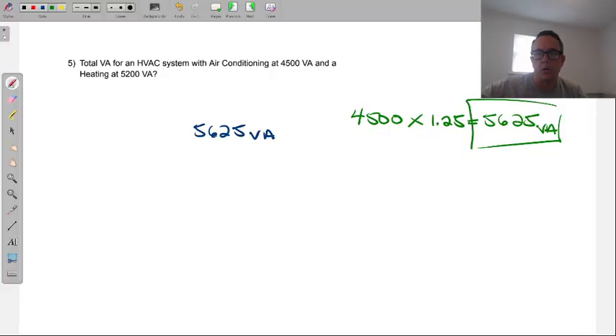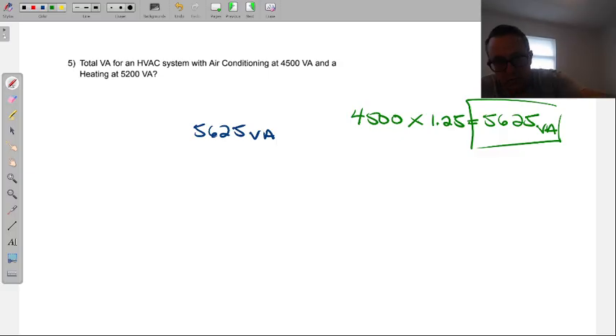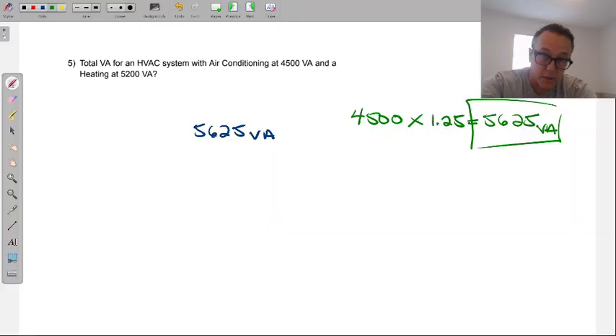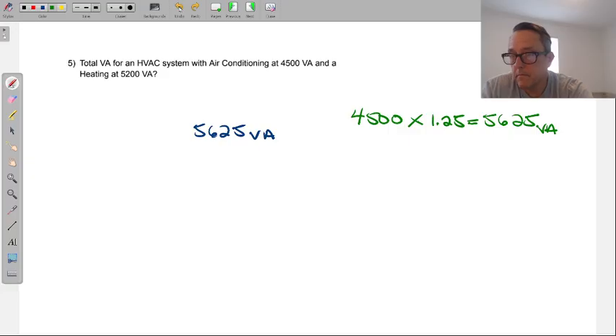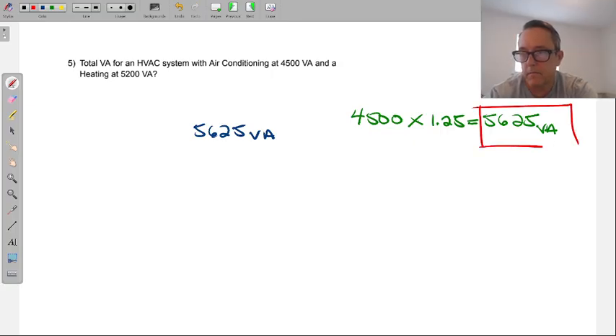So this is the load that we will use to size our main breaker. By the way, it's the same approach when you're sizing just the breaker that's going to protect the HVAC, but that's just coincidental. Use the smaller number instead of the big number? What's that? Why do we use the small number instead of the big number? No. The correct answer is the bigger number. Oh, yeah. This one now becomes smaller initially, when multiplying. Yeah, why did you pick the 400? Oh, yeah. Okay. All right. So good. All right. So why do we pick that one?